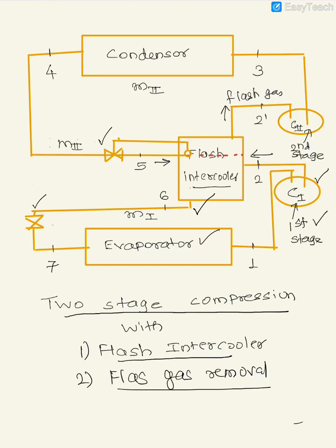Dear friends, I would like to explain two-stage compression with flash intercooler and flash gas removal. This schematic which I have drawn shows a flash intercooler. It is actually a flash chamber used as an intercooler, so it is known as a flash intercooler. The compression happens in two stages: compressor 1 and compressor 2.